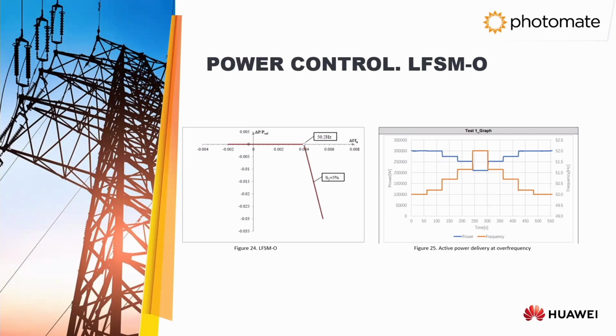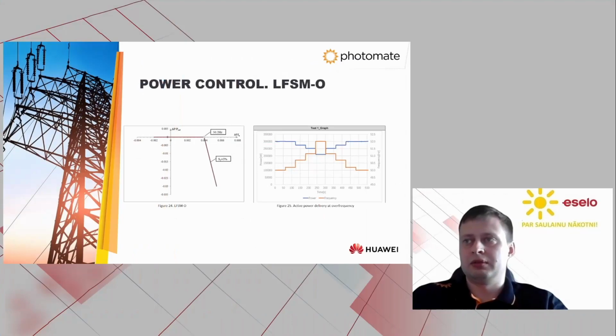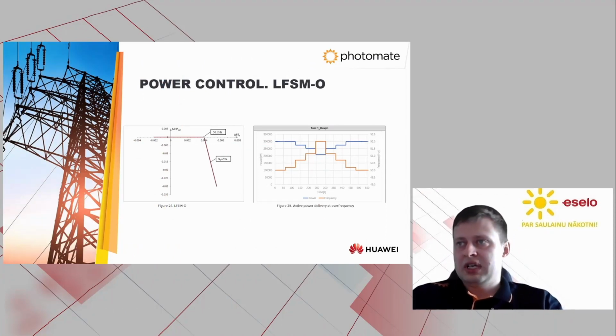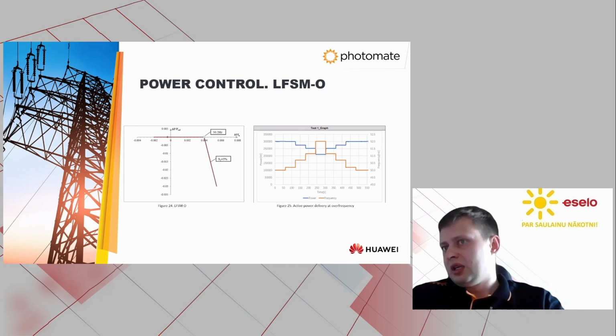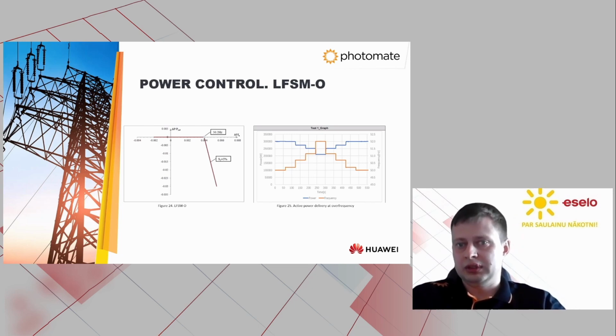In the opposite situation, where the frequency of the power system rises, the inverter must do the opposite. When the frequency rises, the inverter must decrease the output power. I know this is a requirement in Latvia, and it is also possible with solar inverters. This feature is called limited frequency sensitive mode. It must be changeable. The statism is usually 5%, but all the DSOs ask for changeable limits from 2 to 12%.